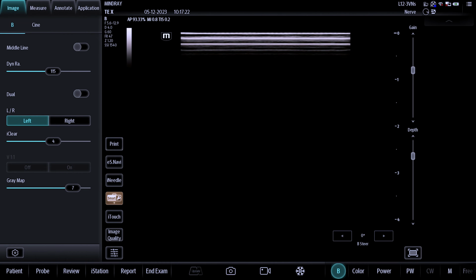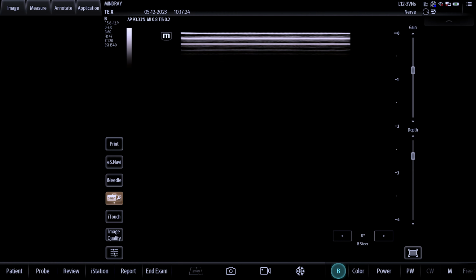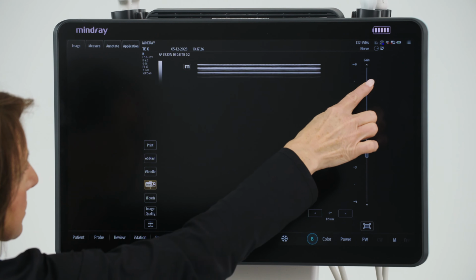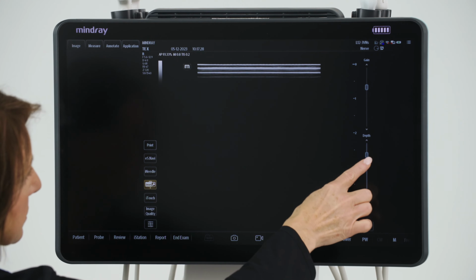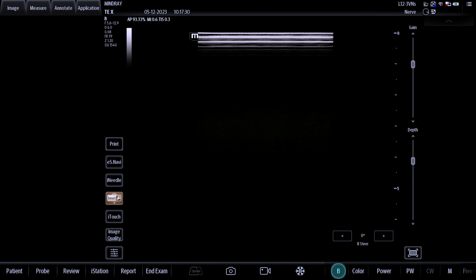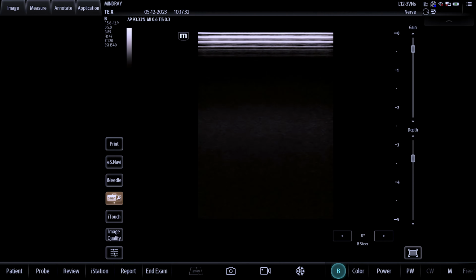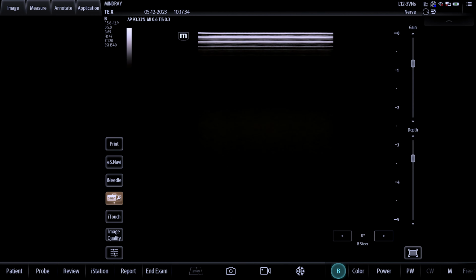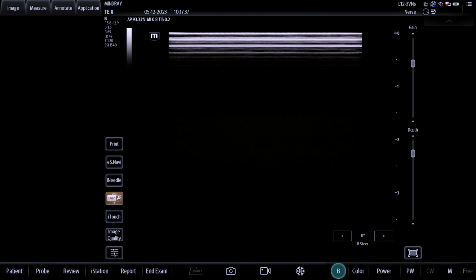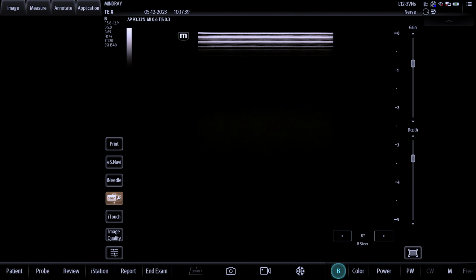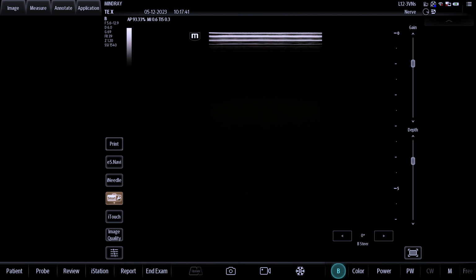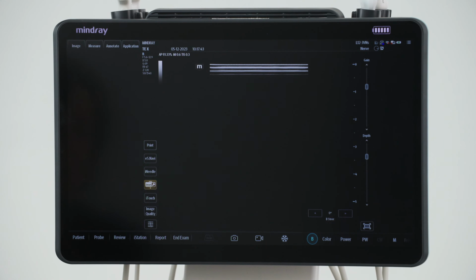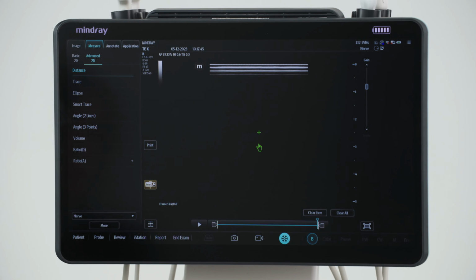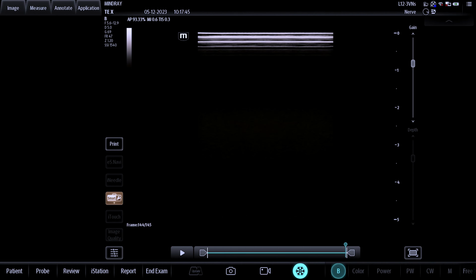The gain and depth controls are located just to the right of the image in either orientation. You can slide or tap above or below the line to adjust. For gain, up is brighter and down is darker. For depth, up is more superficial and down is deeper. Tapping, especially for depth, is recommended for finer, more incremental control. Use freeze to measure, annotate, or print an image. When an image is frozen, there is the ability to cine back to review and save previous frames.